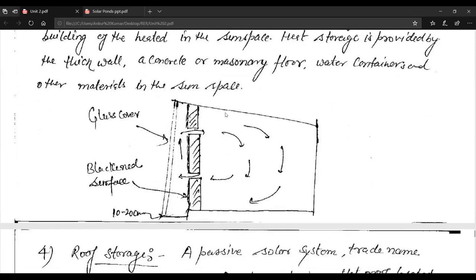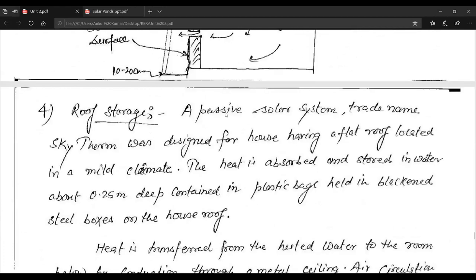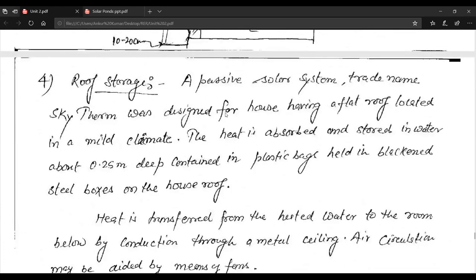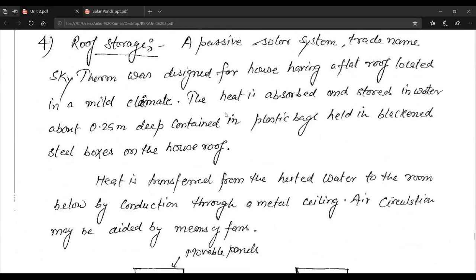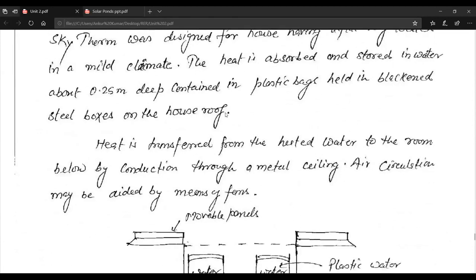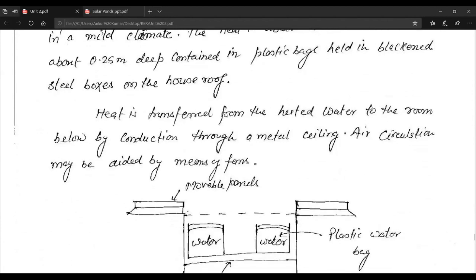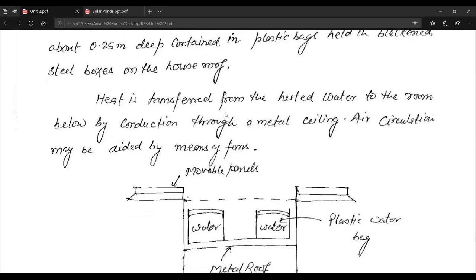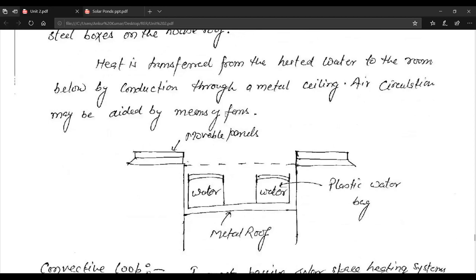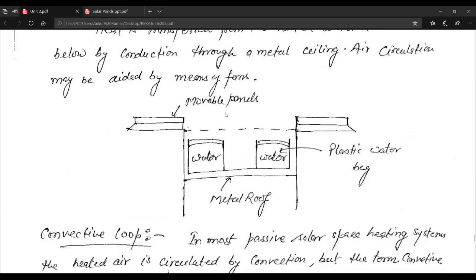Vents near the top and bottom of the wall permit circulation through the main building of heated air from the sun space. Heat storage is provided by the thick wall, a concrete or masonry floor, water containers, and other materials in the sun space. In the roof storage type, the passive solar system called Sky Therm is designed for houses with a flat roof in a mild climate. Heat is absorbed and stored in water about 0.25 meters deep in plastic bags held in blackened steel boxes on the roof, transferred to the room below by conduction through a metal ceiling.